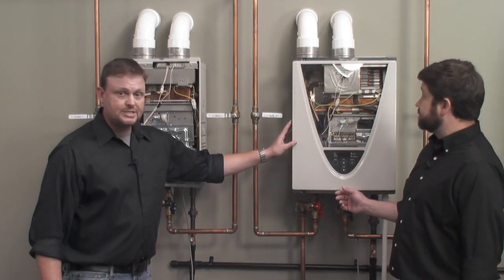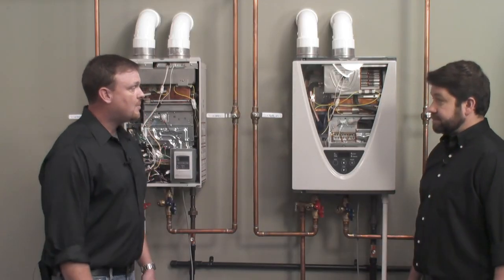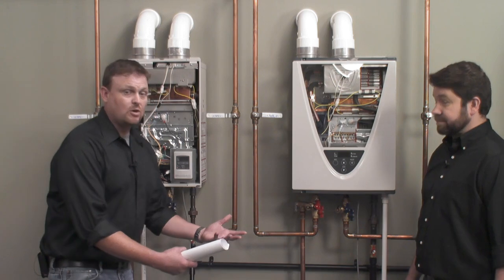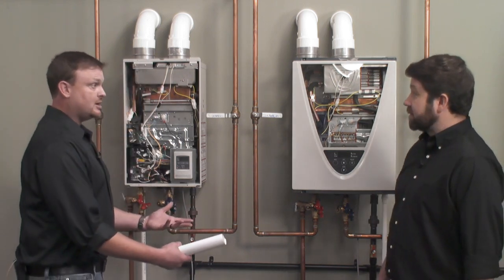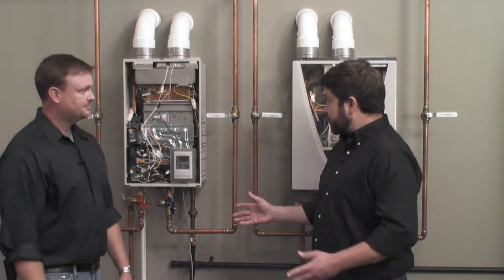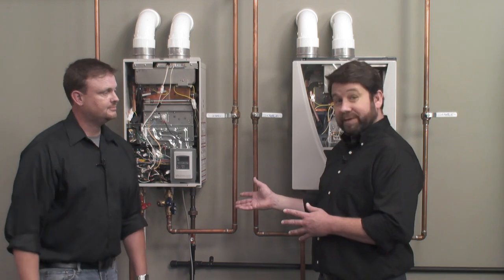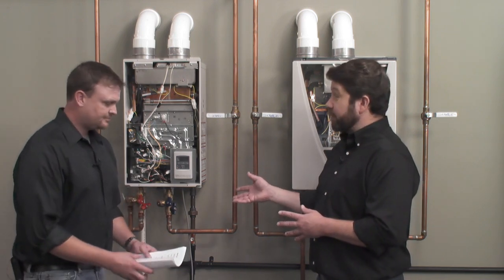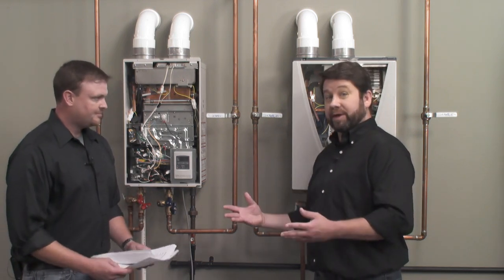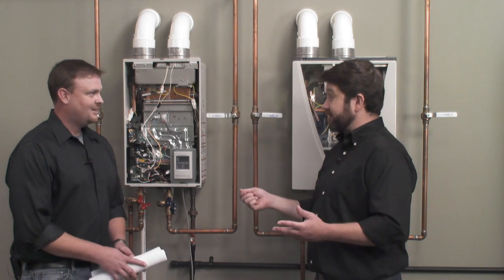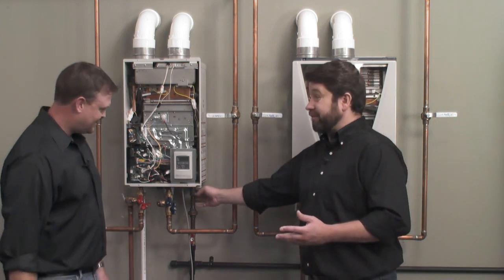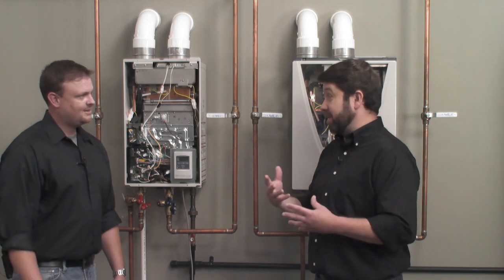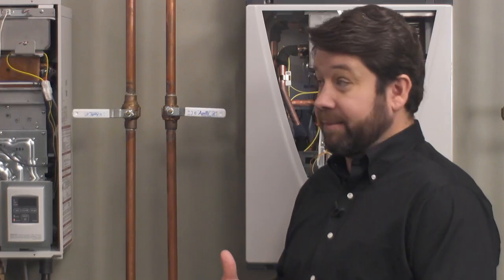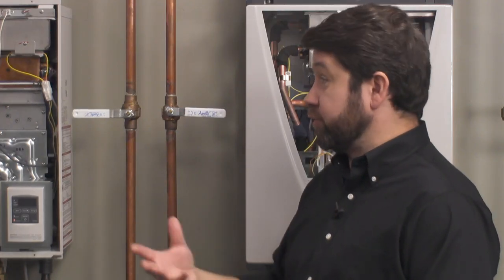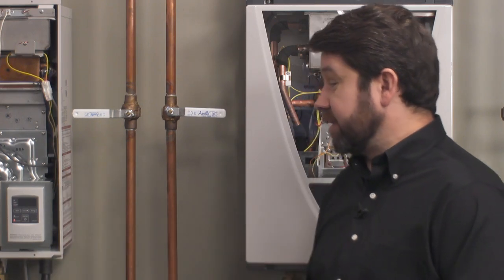Now this is a condensing tankless water heater, but we're offering a new tankless water heater, which is actually 120,000 BTU, the 140. The nice thing about the 120,000 BTU is we can actually use that with most half-inch gas lines that are already in, so in a retrofit where you've got a half-inch gas line run, this will accept the half-inch. With 199,000 BTUs, we needed a lot more fuel, so we had a minimum of 3/4 inch, and you really had to be specific - you might have had to do some resizing. So this is going to fit in a lot more applications.